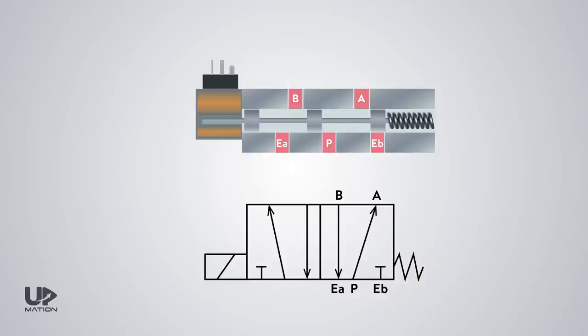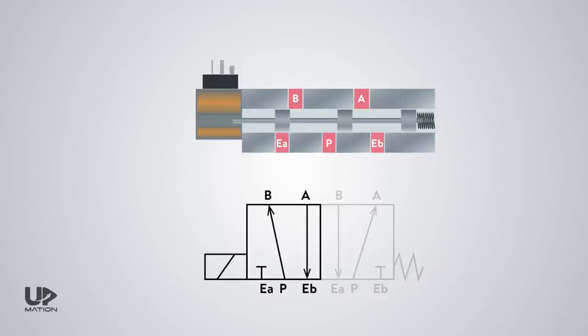In our circuit, when the valve is in its rest position, this square is active. When the solenoid gets energized and the spool changes position, the other one is active. Generally, the square just beside the solenoid sign is active when the solenoid is energized. And this is a rule of thumb for any directional control valve schematic.